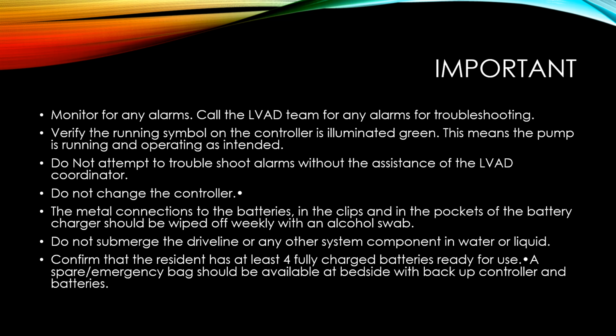The metal connections to the batteries in the clips and in the pockets of the battery charger should be wiped off weekly with an alcohol swab. Do not submerge the driveline or any other system component in water or liquid. Confirm that the resident has at least 4 fully charged batteries ready for use. A spare emergency bag should be available at bedside with a backup controller and batteries.